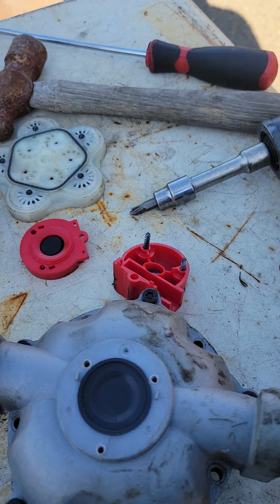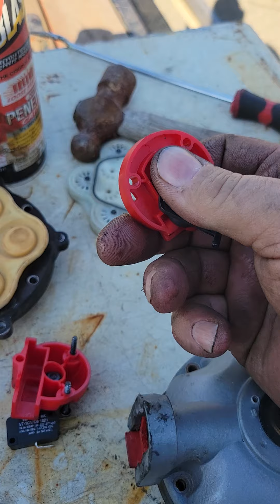So with the pulsating spray out of the wand, it is because of this pressure switch right here. It's on the pump head. When this builds up pressure, it pushes on this button, this little tab right here.